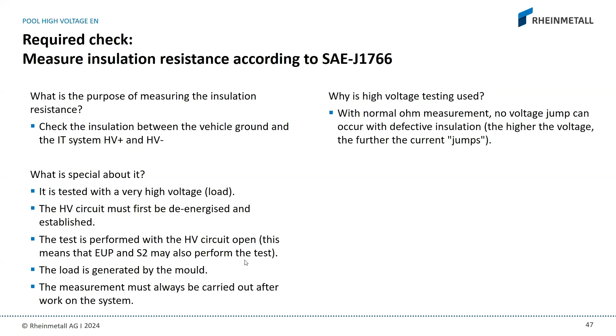So if we have a 400 volt system, we need to put at least 400 volts on the system to check if the isolation is correct or not. If we only use 100 volts, we may not have enough load to reveal the isolation failure.